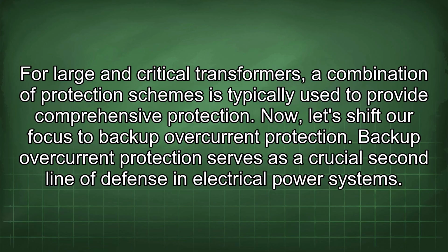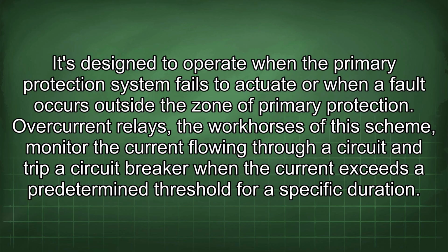Now let's shift our focus to backup overcurrent protection. Backup overcurrent protection serves as a crucial second line of defense in electrical power systems. It's designed to operate when the primary protection system fails to actuate or when a fault occurs outside the zone of primary protection. Overcurrent relays, the workhorses of this scheme, monitor the current flowing through a circuit and trip a circuit breaker when the current exceeds a predetermined threshold for a specific duration.